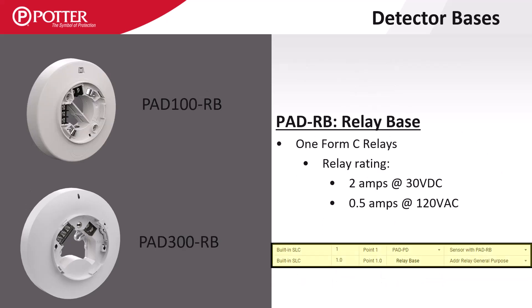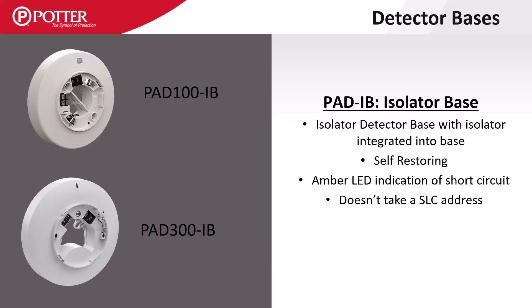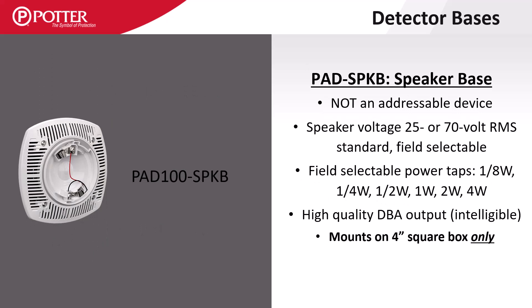The PAD RB offers a fully mappable Form C relay that becomes a sub-point of the detector it's housing. The PAD IB isolator base includes self-restoring short circuit isolation for the SLC circuit. The PAD SPKB is a speaker base that is not an addressable device — it has a speaker attached, so it requires SLC wiring for the detector in addition to the speaker circuit. The speaker base can only mount on a 4 square box.